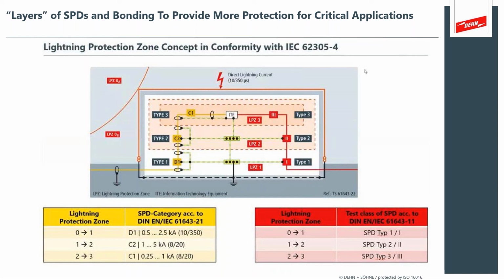Yes, I just want to mention as well, while we're on the topic of voltage control and voltage protection levels and those type of ratings for surge protection devices, remember that a surge protection device will have a voltage protection level rating of a certain amount of voltage. But remember that when you install this surge protection device into a panel and you have conductors from the power bus bars to the SPD and from the SPD to a grounding connection, the voltage drops that you are going to see over these conductors need to also be taken into consideration, as these can increase the overall voltage protection level that the device will provide. So it's very important to take that into consideration when you install SPDs as well.